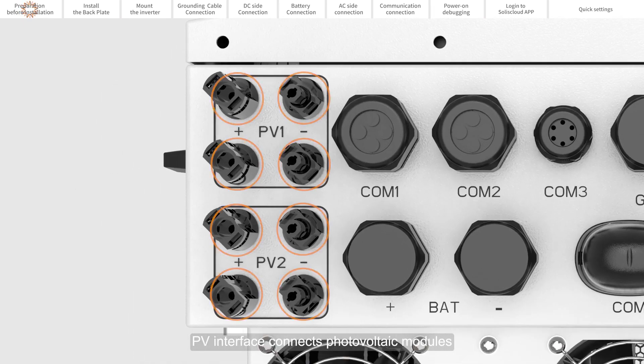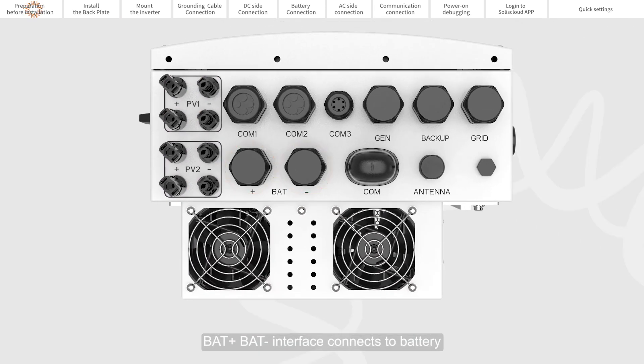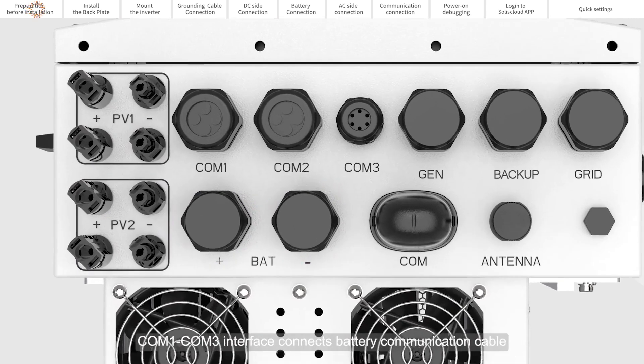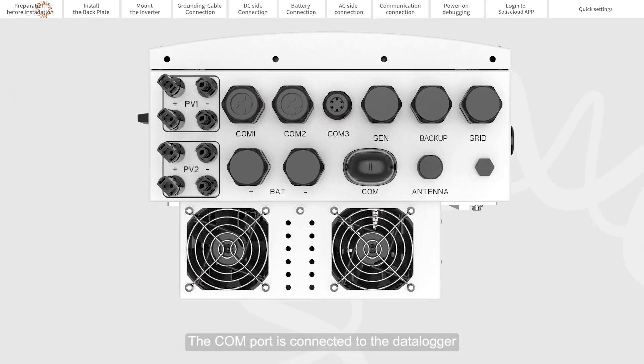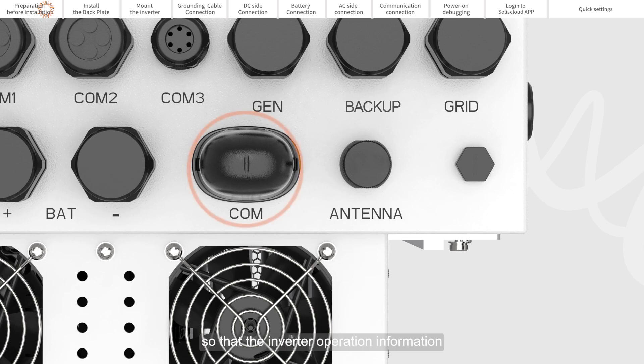The PV interface connects photovoltaic modules and inputs photovoltaic energy into the system. BAT plus and BAT minus interface the battery. COM1 through COM3 interface connects the battery communication cable, the CT wire, the parallel cable, and the generator communication cable. The COM port connects the data logger so that the inverter operational information can be uploaded to the SolisCloud platform.